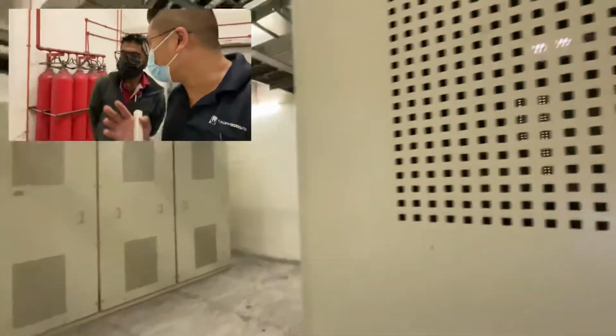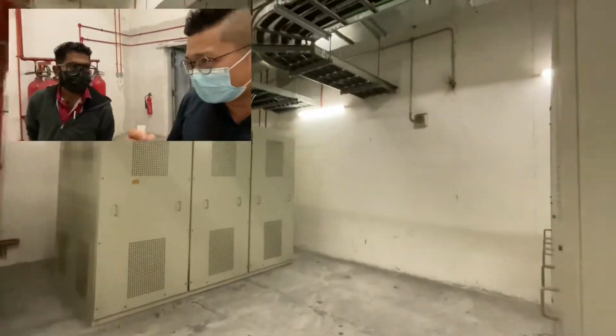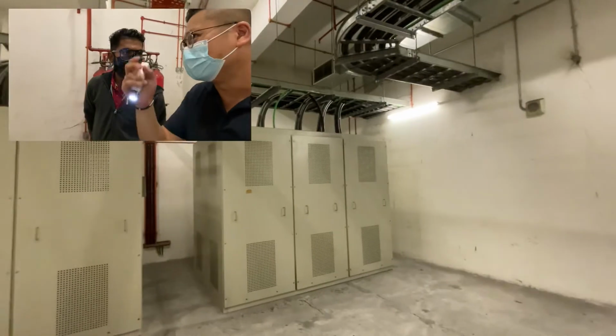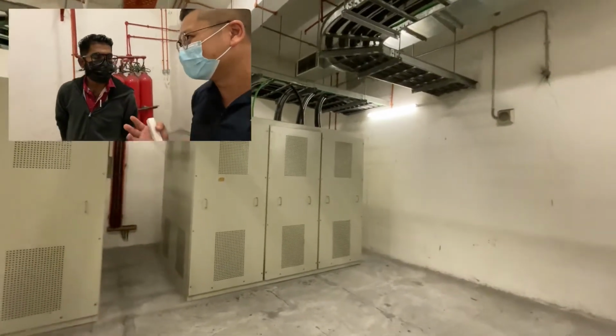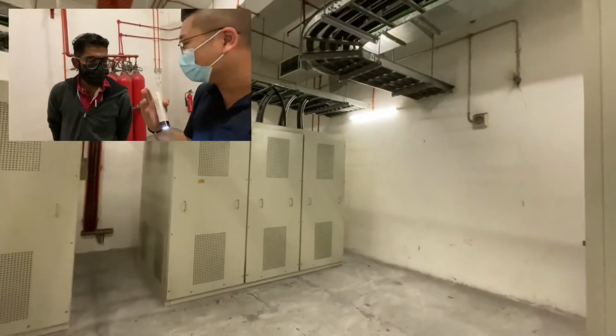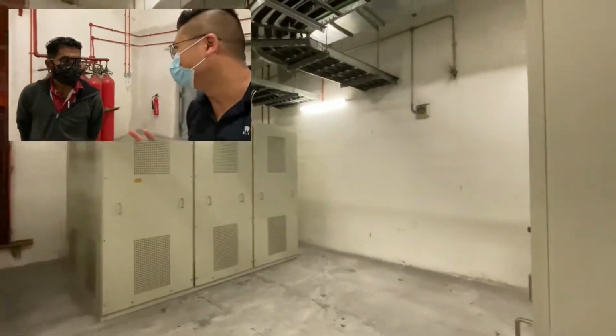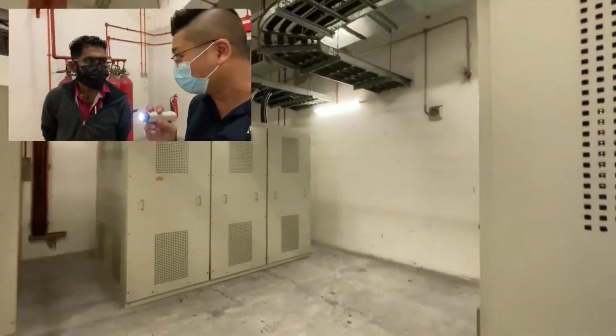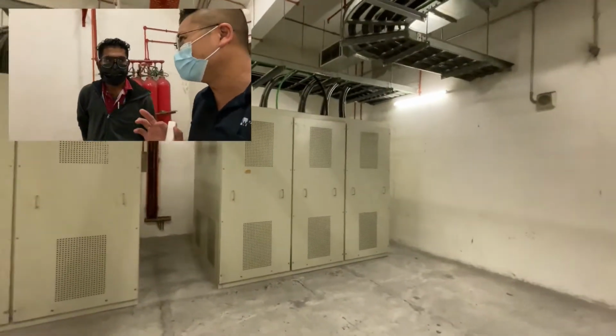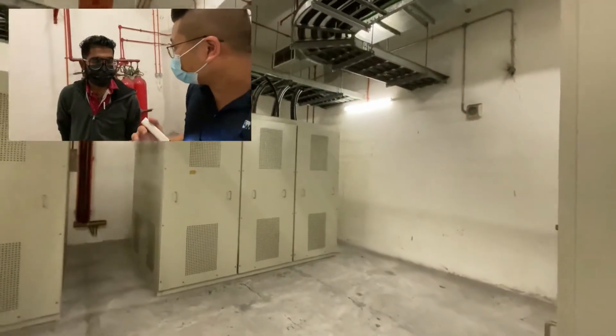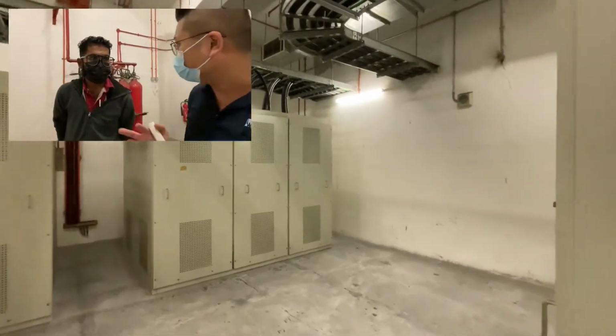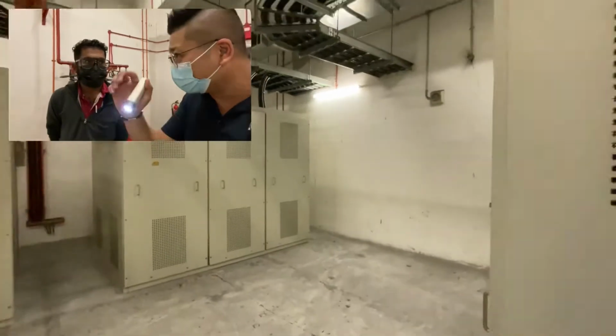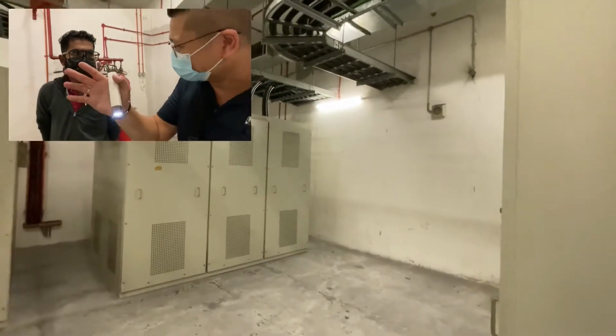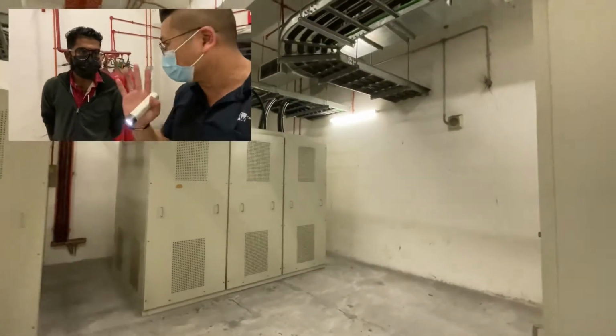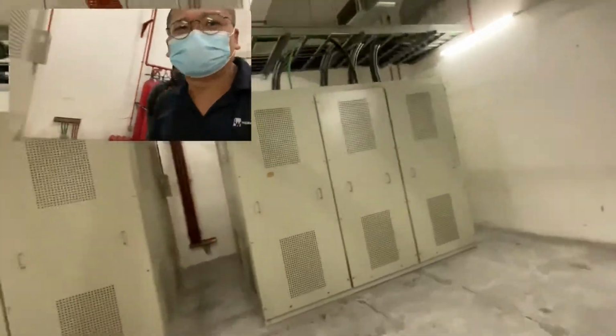So for the tenant transformer, if the temperature is below the alarm setting point, no problem. This one can go until 150 degrees Celsius. Above that only it changes, and before that we already give an alarm. But now it's just 62 only, right? So no need to worry, no problem.